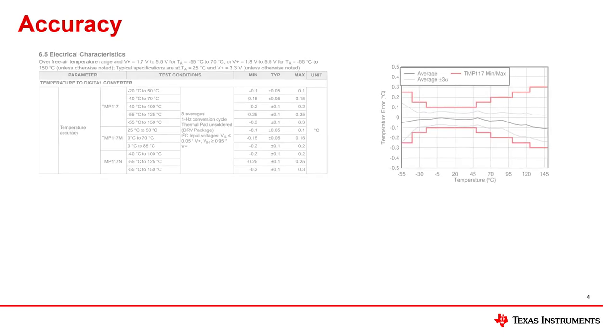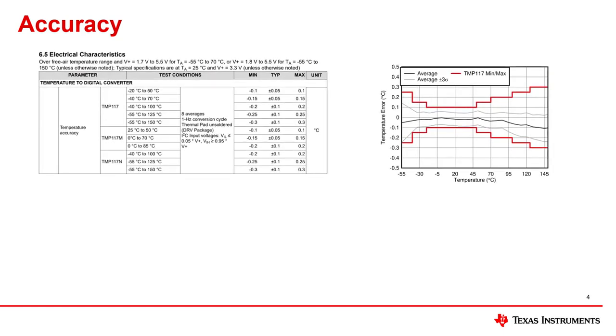Accuracy specifications represent how close the measured temperature is to the true value. System accuracy requirements will usually come from application-specific details. For example, most medical applications require a high standard of accuracy, and human body temperature must be measured within plus or minus 0.2 or 0.1 degrees Celsius. Other systems, such as motor control or over-temperature shutdown mechanisms, may not have the same high accuracy requirements. In these cases, one or two degrees Celsius may be more than enough for proper operation. Most often, datasheets will represent this as an absolute value relating to the typical and maximum temperature error in degrees Celsius.